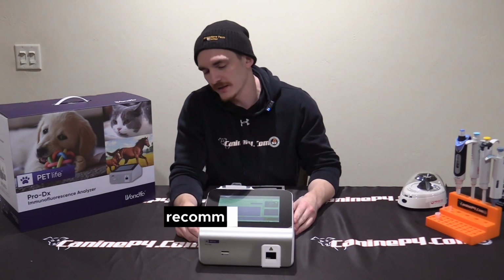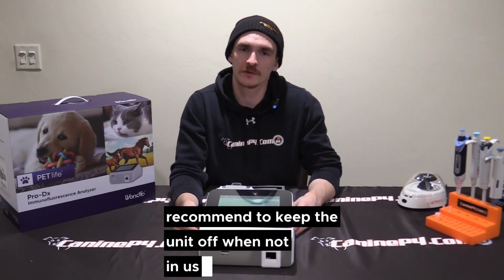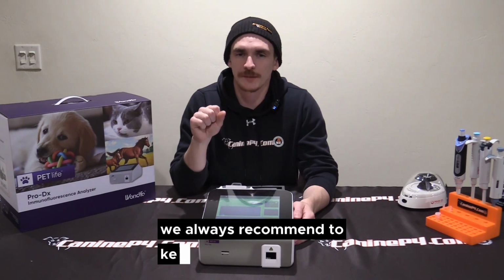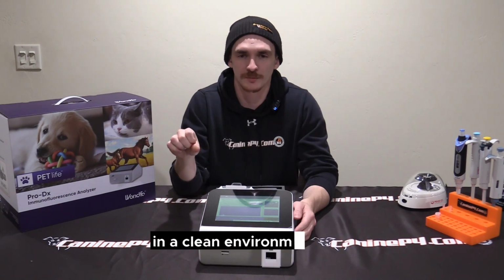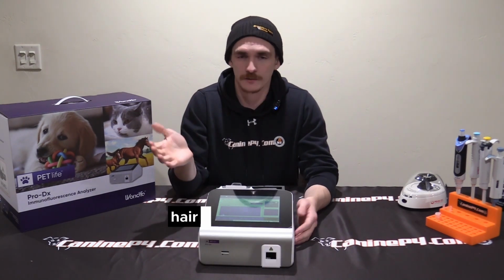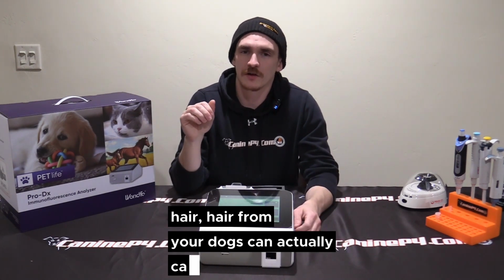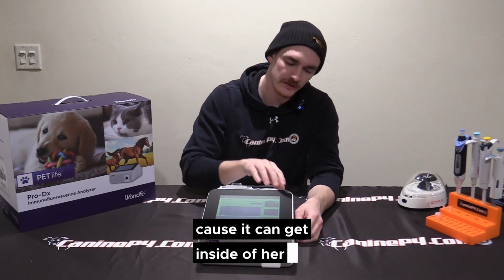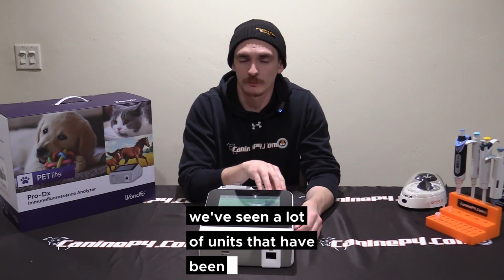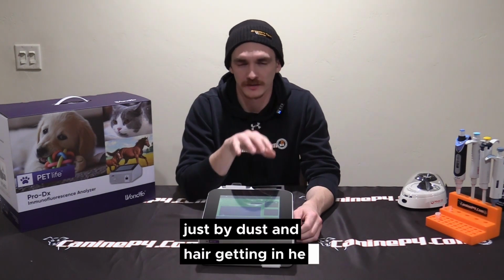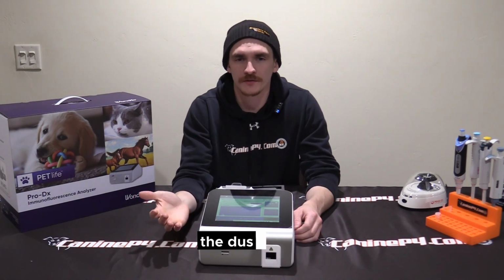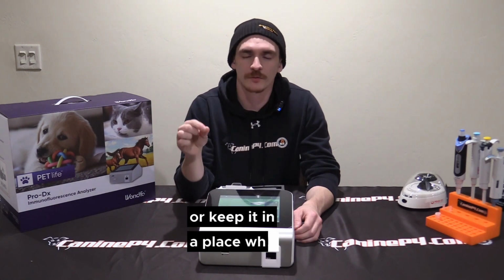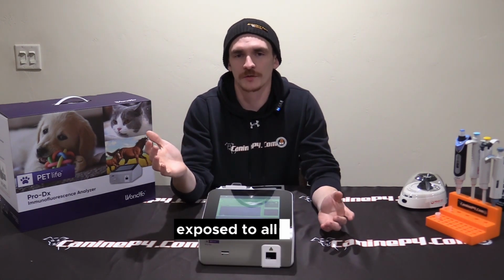So we always recommend to keep the unit off when not in use. Secondly, we always recommend to keep your Finecare in a clean environment. Dust, hair from your dogs can actually cause issues because it can get inside of here. We've seen a lot of units that have been ruined just by dust and hair getting in here. So either cover it up, the dust cover, or keep it in a place where it's not going to get exposed to all those kind of contaminants.